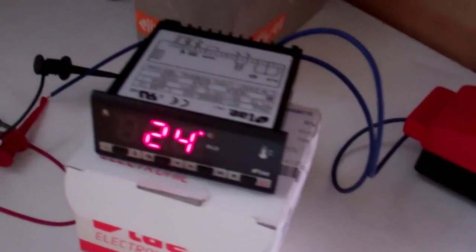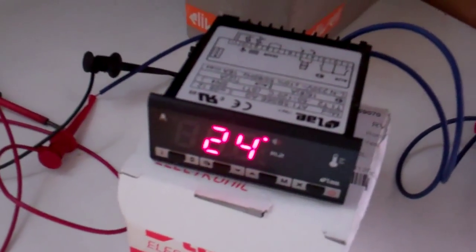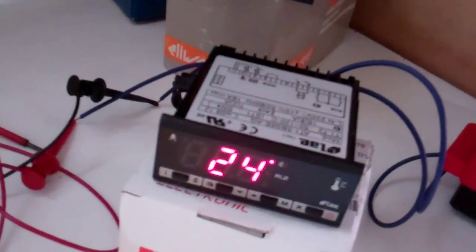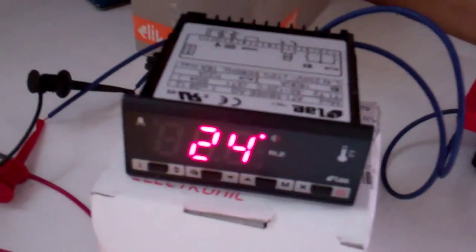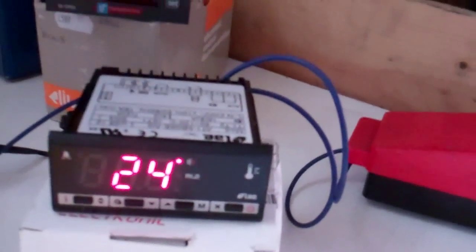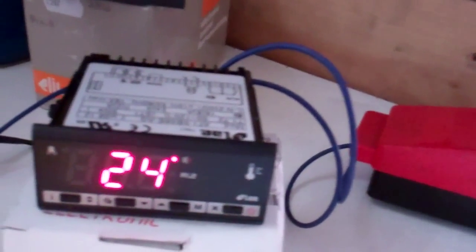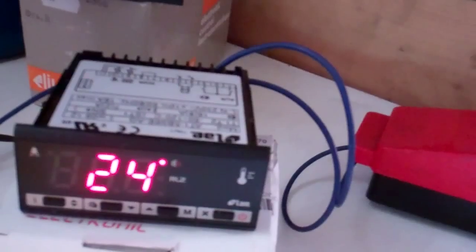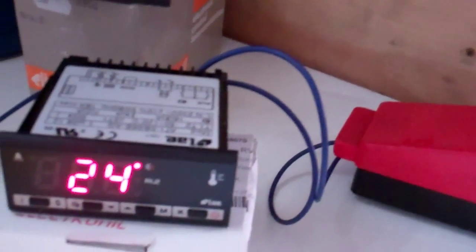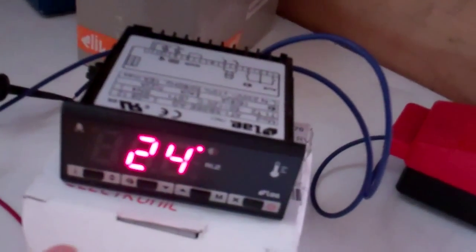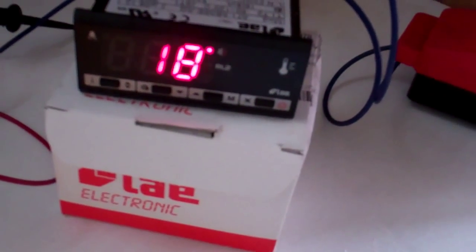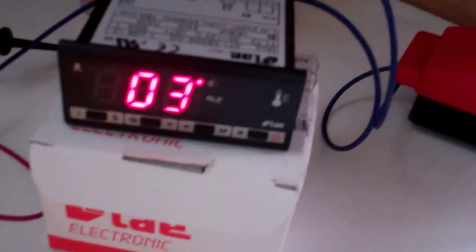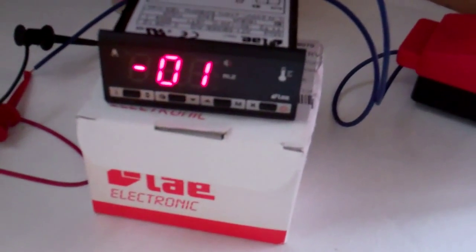Just going off of that. I had one the other day I had a display that was reading 2.6 I think it was. And I put a new probe on there, it was fine. And then I installed the probe and it was still reading 2.6. And it didn't move. And then I wondered whether it was the display that was faulty. If I'd had this little box on there I could have flicked some switches up and down and seeing the temperature change.